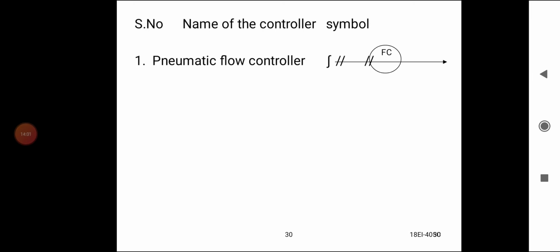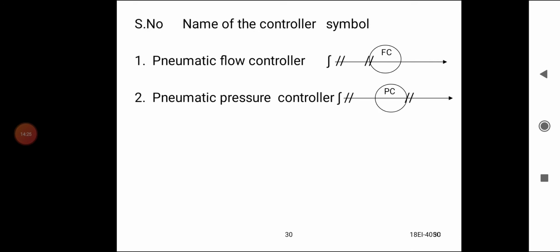So FC indicates the first letter is pneumatic flow, the second letter is controller. The double lines indicate a pneumatic valve, pneumatic signal.